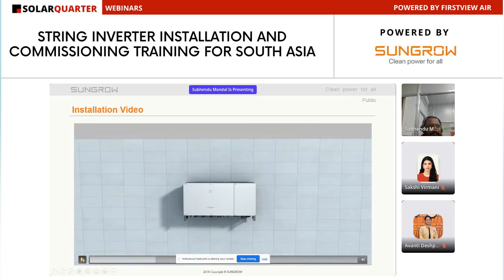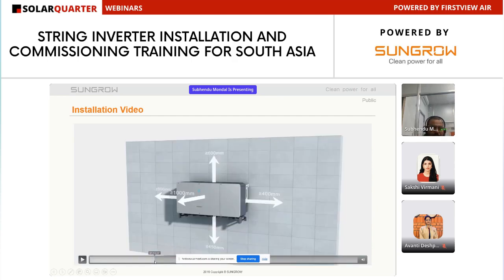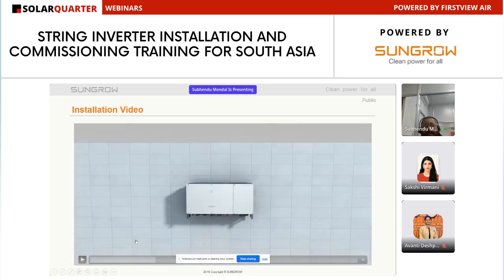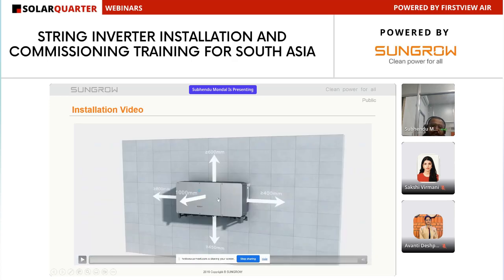So here is the clearance of the inverter: ground clearance, front and back clearance. Left side clearance should be more than 1000 mm, top clearance should be more than 600 mm, right side clearance should be more than 400 mm, ground clearance should be more than 450 mm, and front clearance should be more than 1 meter.